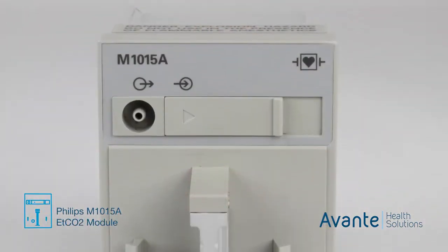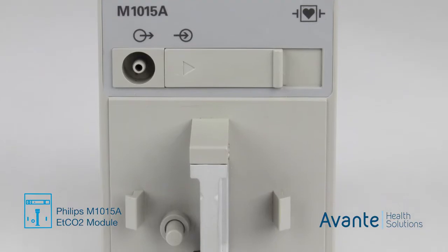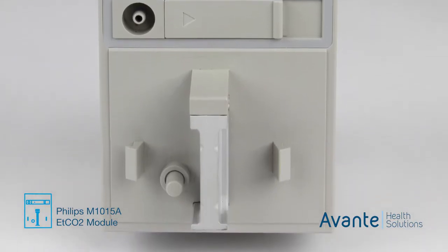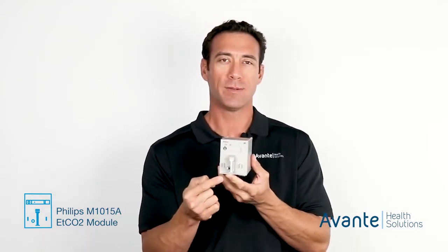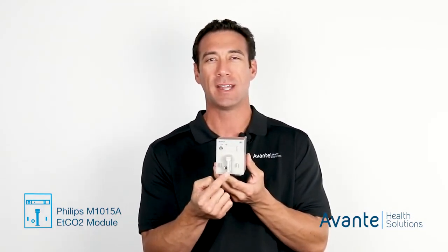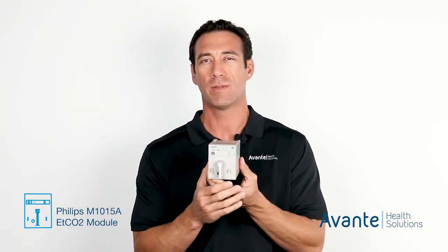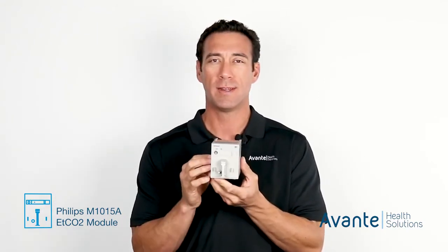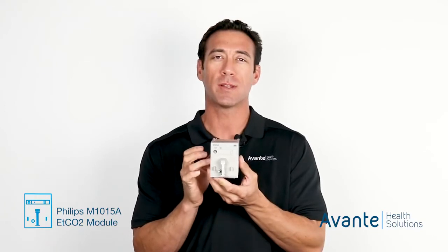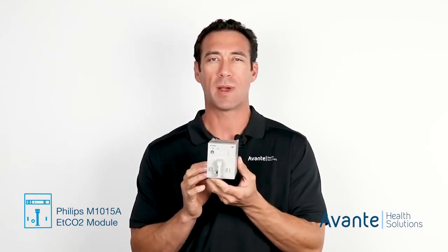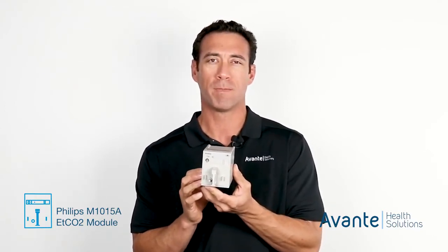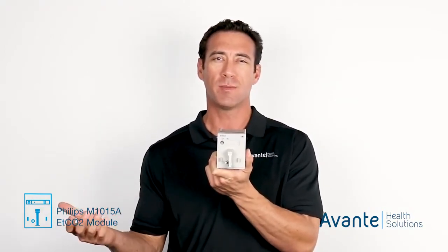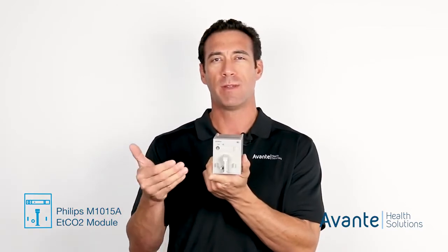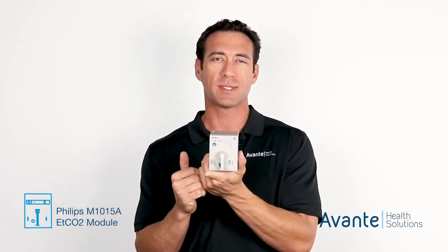Now I'm holding the Philips M1015A, and this is specifically going to measure EtCO2. So it will plug in a little cable to the front, and it's going to attach to the patient's respiration tube, and then you're going to get side stream sampling on CO2, respired CO2 from the patient. So there's two ways of sampling CO2. One of them is going to be mainstream, one of them is going to be side stream. This module is going to take that side stream sample.